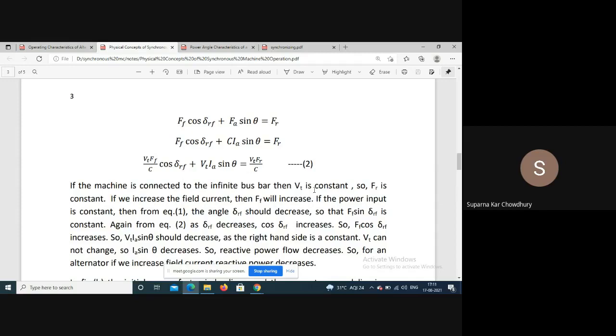was utilized for controlling the line power factor. That is, a synchronous motor without load with a higher excitation was connected. There was some design consideration; this is called a synchronous condenser, to improve the power factor of the line. However, now we have power factor controllers which are power electronic devices.